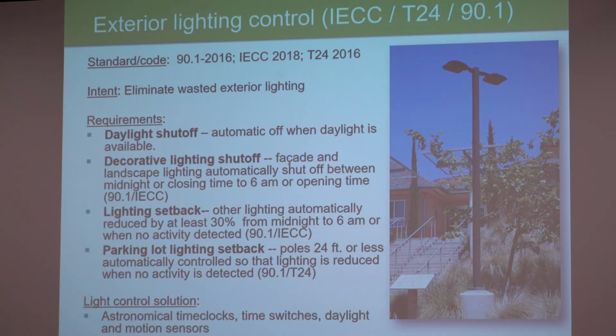Okay, exterior lighting. Exterior lighting control is a key requirement in all the codes. This has gotten more stringent in the latest codes. Basically, the key requirements are that during daylight hours, exterior lights have to be automatically off. Decorative lighting has to be automatically shut off deeper into the night. And when I say decorative lighting, I'm specifically talking about facade and landscape lighting. So deeper into the night, those have to be automatically off.